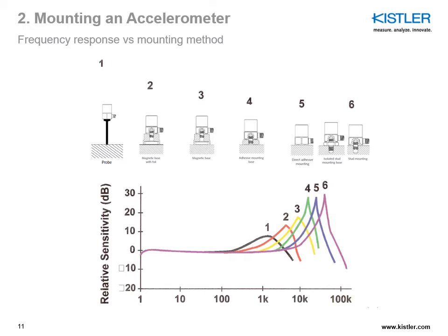Then you have direct adhesive mounting using glue or a very thin layer of wax — this gives resonance peak number five, still good performance but not as good as stud mount. Next is number four: adhesive mounting base usage, where a stud and separate plate are used together, adding mechanical filtering so the frequency response resonance peak arrives much sooner. Then number three is magnetic mounting — mostly due to the weight of the system, you are very limited in frequency response (yellow curve). Number two uses a magnetic base with a foil in between for isolation, adding another mechanical layer and further reducing frequency response (red curve).